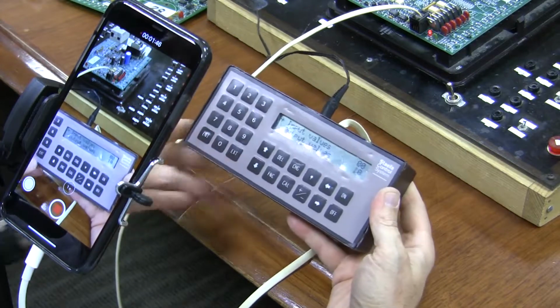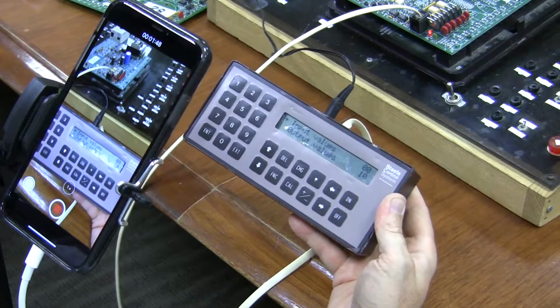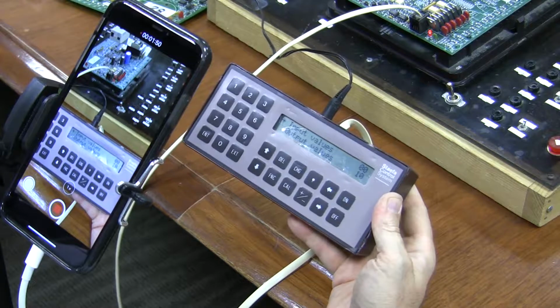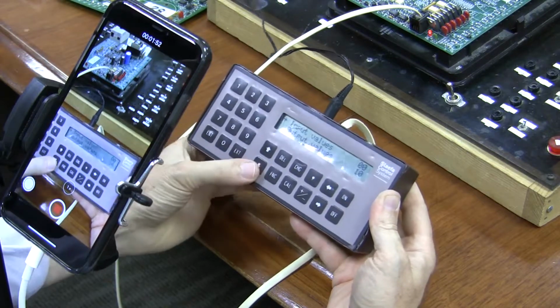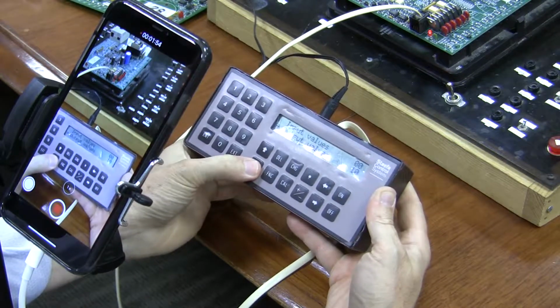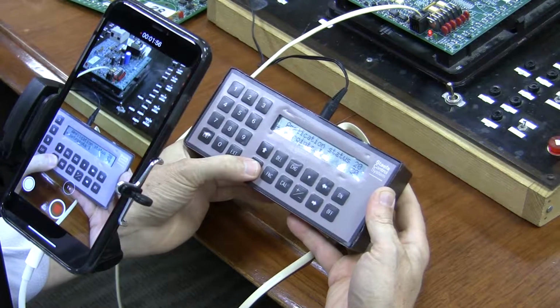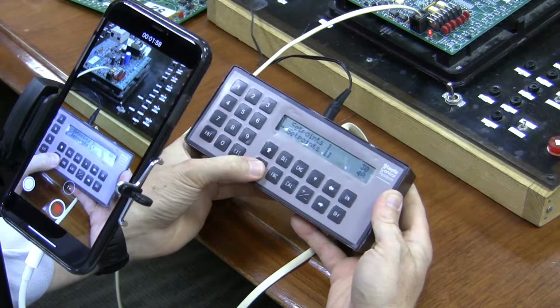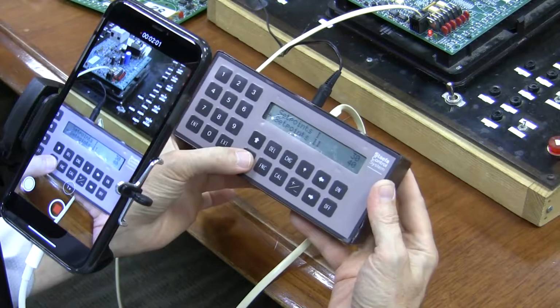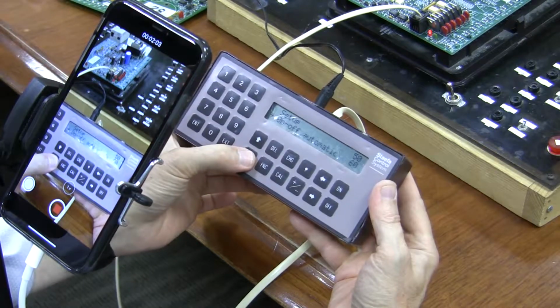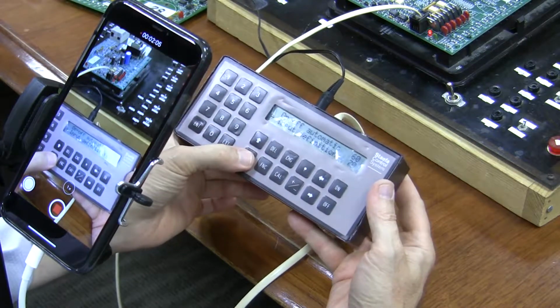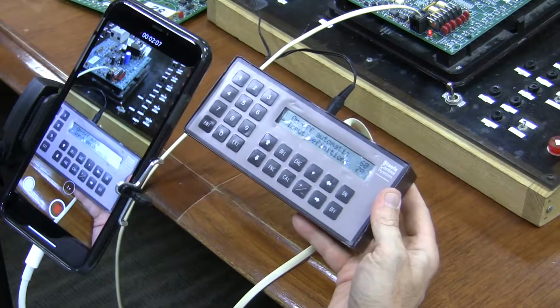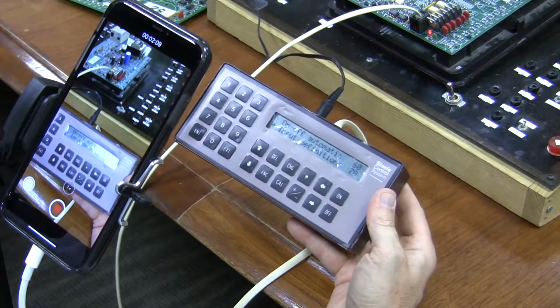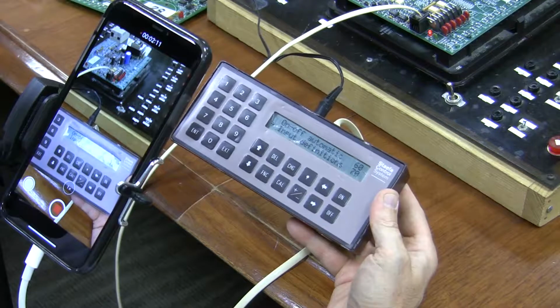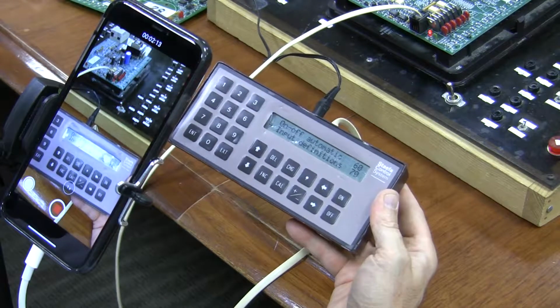Okay, so at this point, I want to just show you some of the other parameters in here. Okay, we're going to scroll by the 10s. We did application status, we did set points 2. We did setup, and we did on-off automatic. The next one here is where I get to tell it, when I wire something up to this card, say I wired up to XYZ input, this is where I go tell it what I have wired up to a card.